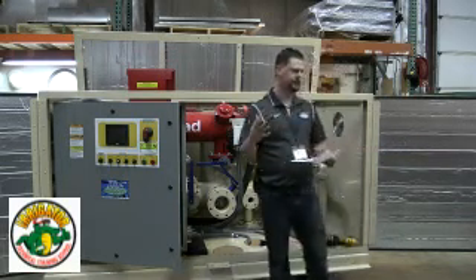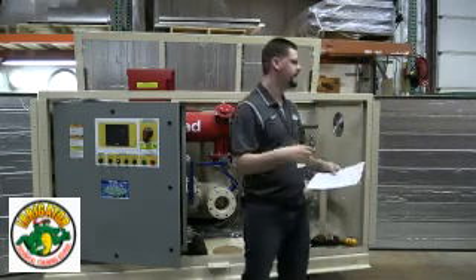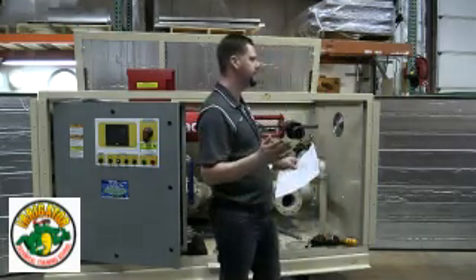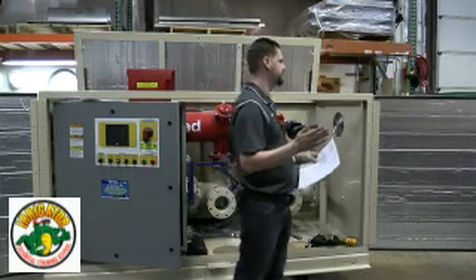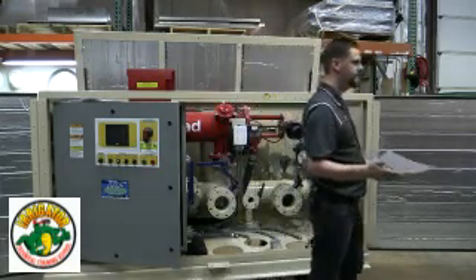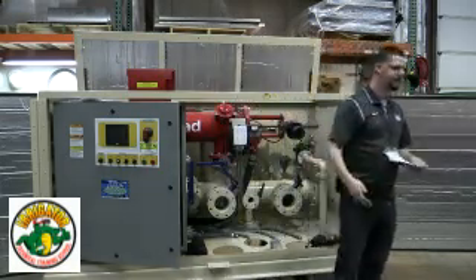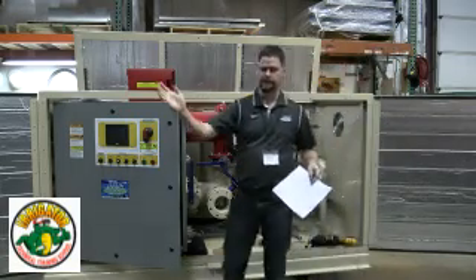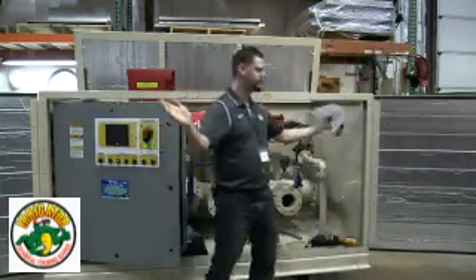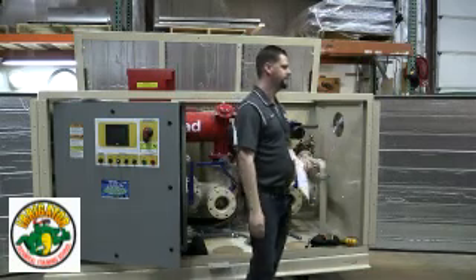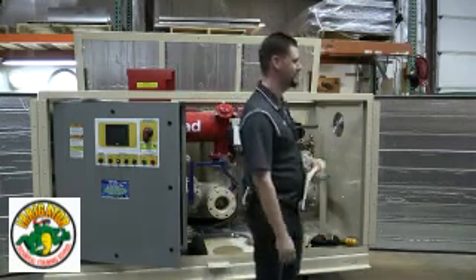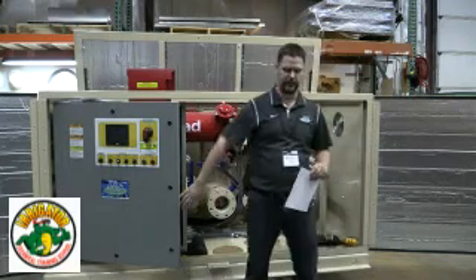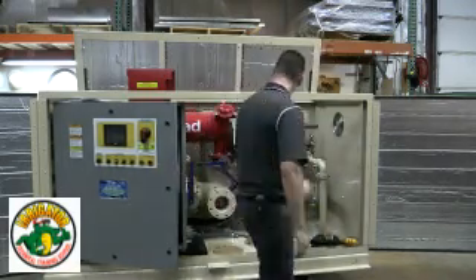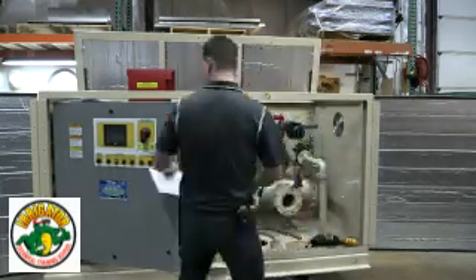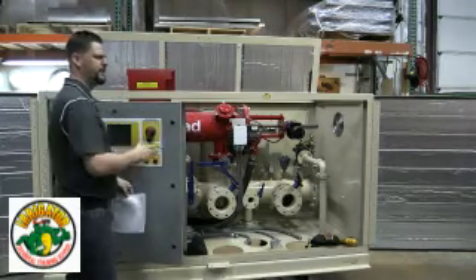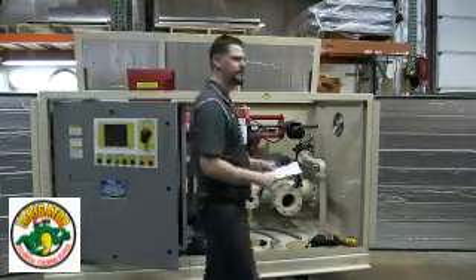So let's talk about pressure gauges. Our pressure gauges are a mechanical device, just like any, imperfect. Now, if we walk up to a pump station, and I have one gauge over here that says 80 pounds and one gauge over here that says 20 pounds, we know there's something wrong. Probably with a gauge. But the moral of that story is check this gauge and that gauge. They should match the pressure here within a little bit. I mean, come on, we're not perfect here.